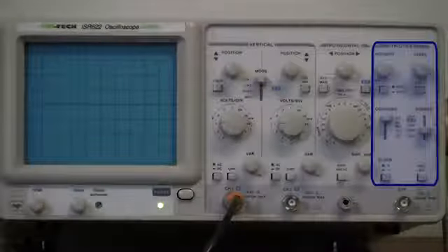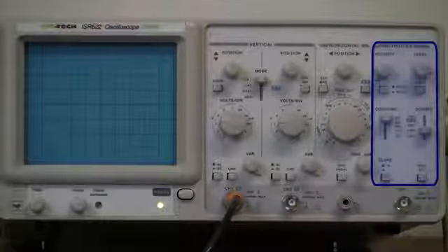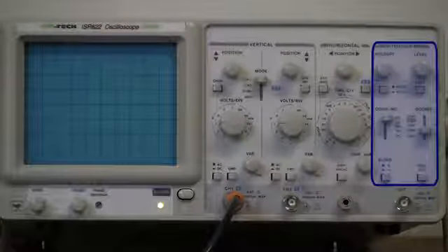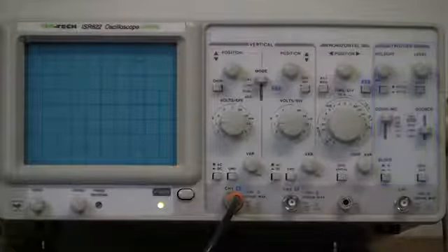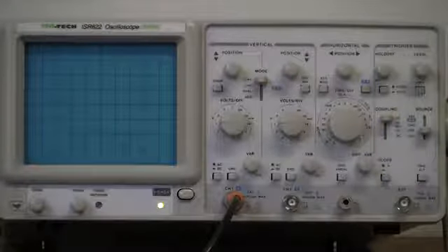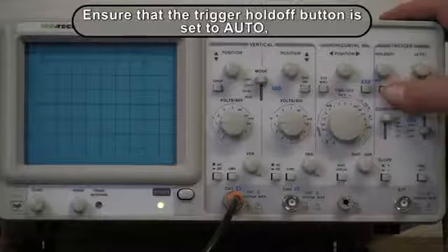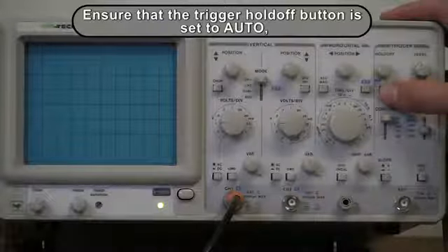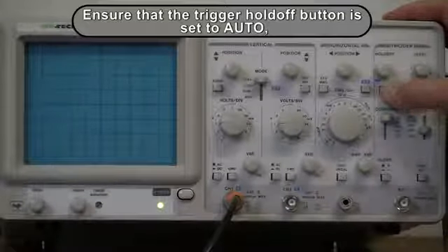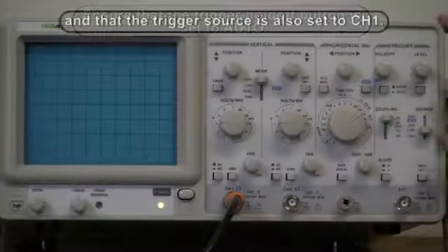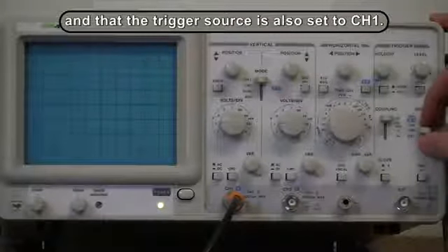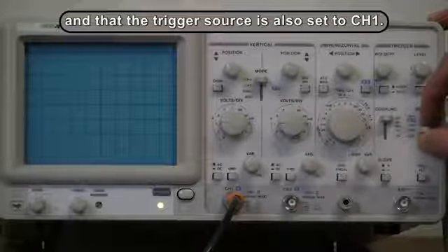The group of trigger controls on the right of the oscilloscope is used to ensure that the input signal is displayed correctly on the oscilloscope screen. Ensure that the trigger hold-off is set to auto by pressing the button in, and make sure that the source channel is set to the same channel that the input source is connected to, in this case channel 1.